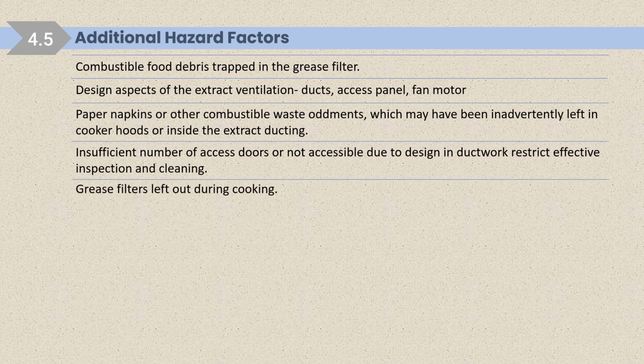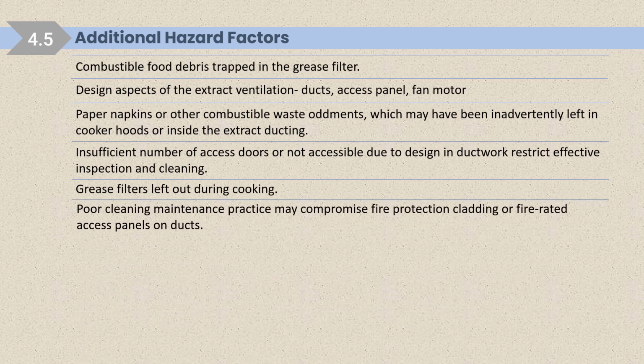grease filters left out during cooking. I've seen it in some kitchens where people are not aware. Suppose the ventilation system, the exhaust system, is weak. They simply remove the filter so that the exhaust can work properly, and that may cause fire also. Poor cleaning and maintenance practice may compromise fire protection cladding or fire-rated access panels on the duct.